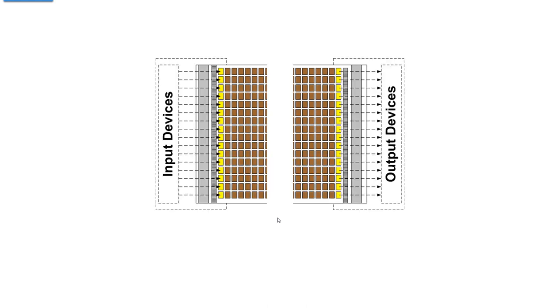If we take a closer look at these, I took the liberty to change the color from brown to yellow. The input field devices can be all different voltages, anywhere from 5 volts to 480 volts. The coils of those yellow relays have to match the field device voltage, the field wiring interface to the relay panel. Those yellow relays they're all going to have the same coil voltages as the brown relays, but the contacts on the right end for the output devices, those contacts have to be able to handle the voltage and the current for the output devices.